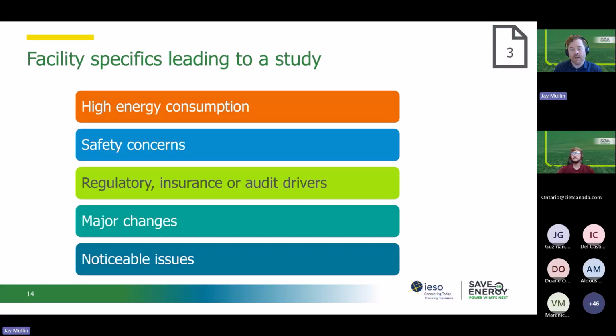So it becomes more recommended to undertake air balance studies if you are experiencing some of these symptoms. And part of the reason for that is that, as a general rule of thumb, fixing pressure imbalance can reduce HVAC costs by 15 to 30%. Of course, this isn't guaranteed. And often when it comes to air balance studies, the primary driver is safety, air quality, comfort. But again, depending on your energy use and the size of your facility, there can be significant energy savings as part of that.